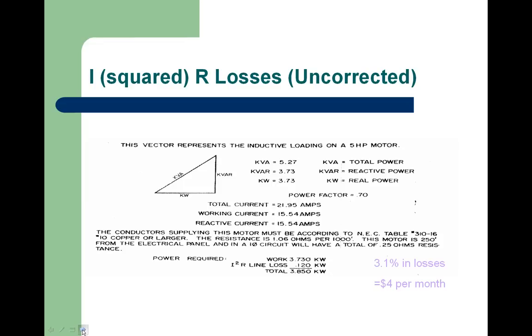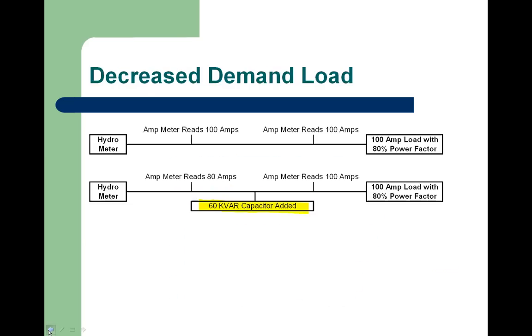As I mentioned earlier in one of the slides, I'm just going to jump back here to this particular decreased demand load. This sometimes is used on sub-services, both in commercial and in industrial, where you may have a splitter or a secondary panel, maybe 500 feet or more from the main switchboard. If we use this 100 amp load as an example, if this was a 100 amp panel with 100 amps on it, you sometimes could blow the fuses to that.